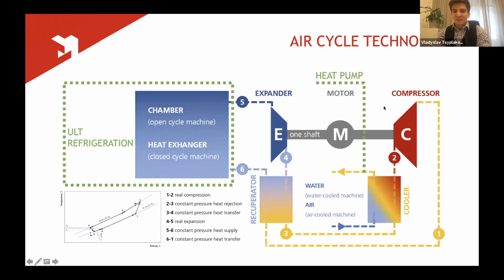So coming down to this refrigeration cycle that we use in our refrigeration machines, here we have a centrifugal compressor sharing a shaft with the centrifugal expander. And between them is the electric motor. Usually the airflow goes something like this. The air is heated in the compressor, cooled in a series of heat exchangers. First, we have the end cooler. We're going to look at this one a little closer later. And then we have the recuperative heat exchanger. After that, the air is expanded and can become ultra-low temperature and can be supplied directly into the chamber or to a heat exchanger, which is located in a chemical process. After that, the air goes to the recuperator and back to the compressor.